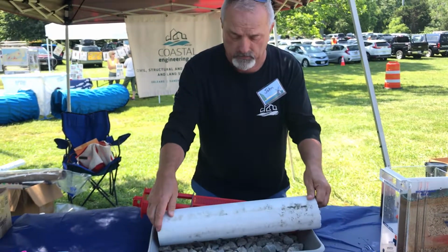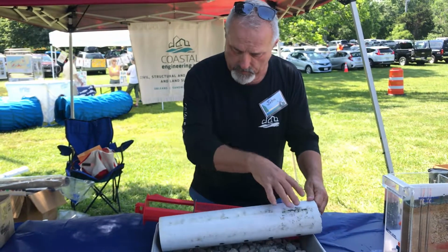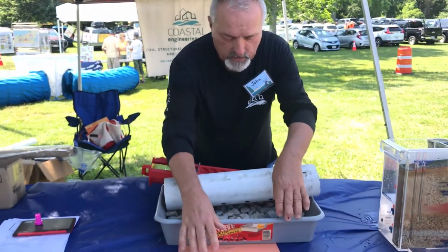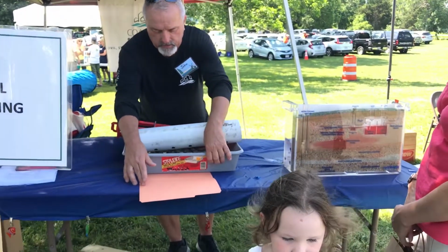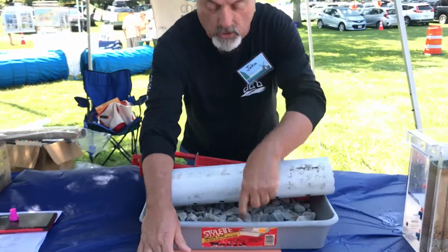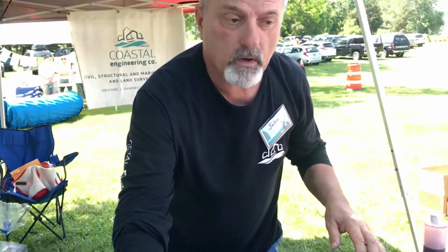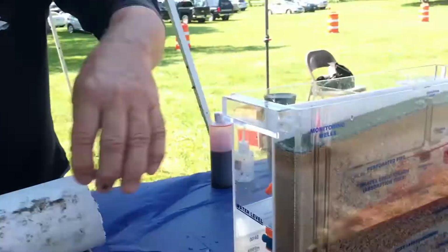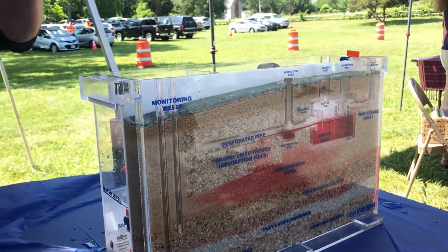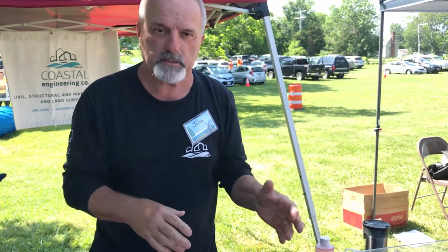Typically they're turned down. Water goes through, goes into the stone, percolates through the stone. We'll pretend like the gray here is the sand, and then it'll actually end up at that stone-sand interface, and then we'll percolate through the sand and actually down into the groundwater. And as you can see, the green and the red show that there is great filtering throughout a typical Title V septic system. Still, it doesn't filter everything out, so you've got to be careful what you put into the system.